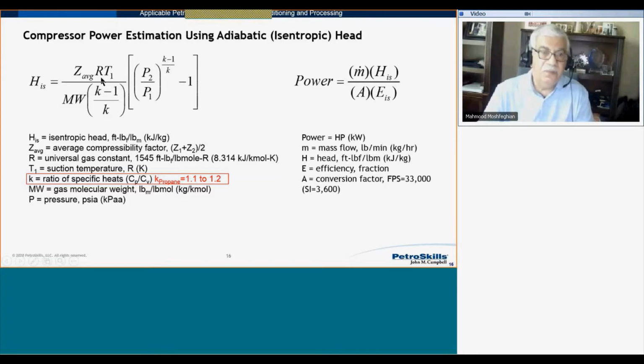So as you see, the important parameter here is the suction temperature T1. The lower the T1, the better for the power requirement. Discharge pressure and suction pressure of compressor play an important role on compressor power requirement. K is defined as Cp over Cv here. Heat capacity at constant pressure divided by heat capacity at constant volume. For propane, the range of K is the range of 1.1 to 1.2. So if I say by increasing temperature, condenser pressure goes up, therefore discharge pressure goes up. You can see here how it impacts the head, and if the head goes up, then the power requirement goes up. Just to relate the effect of different parameters on power requirement of compressor.